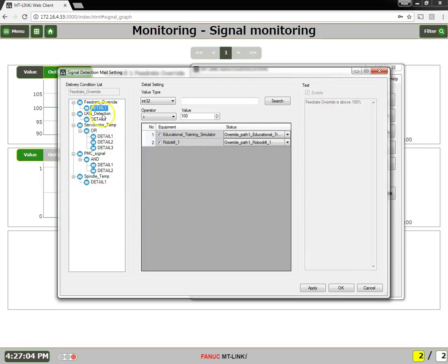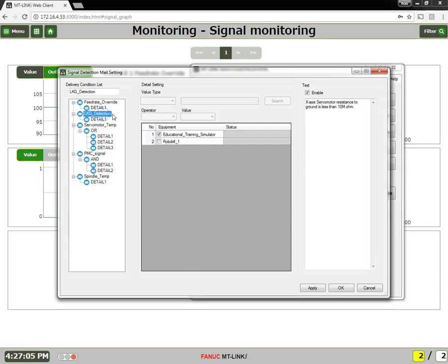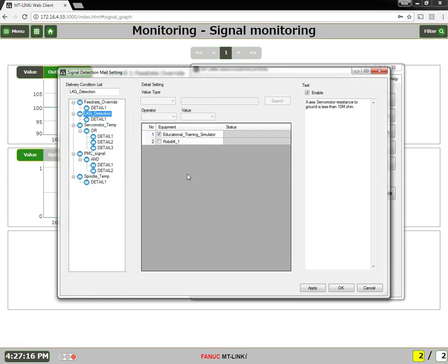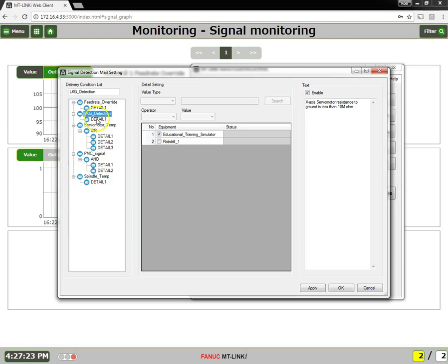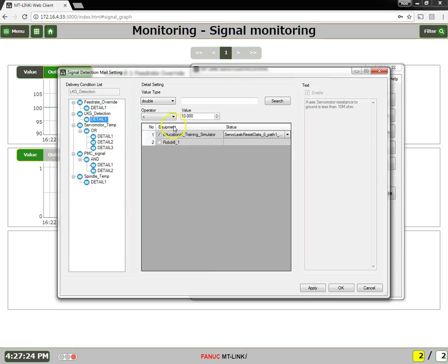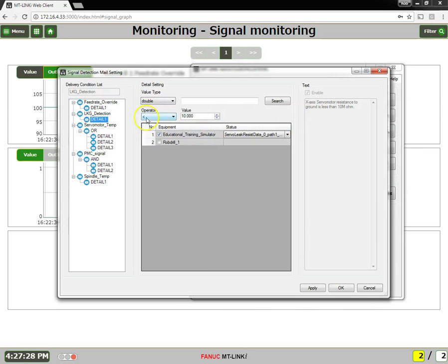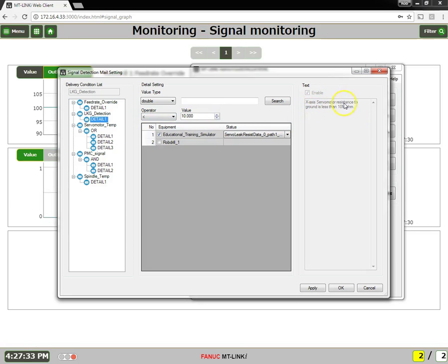Here is a leakage detection. On the newer FANUC Alpha IB servo systems have built in dielectric breakdown resistance checks like a megaohm meter in the drive unit. We can monitor that diagnostic. In this case, if the value is less than 10, which is 10 meg, I'm going to send out an email for that.